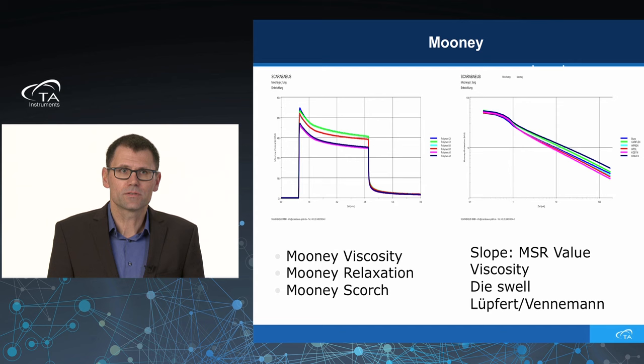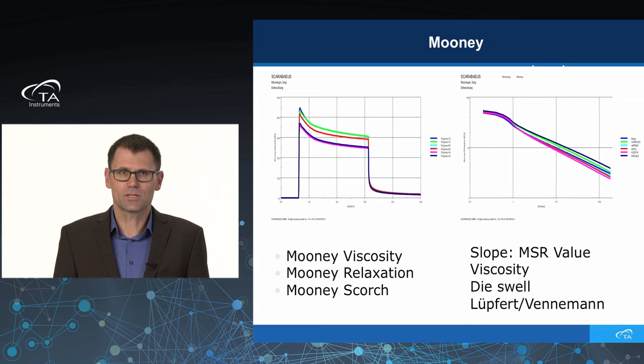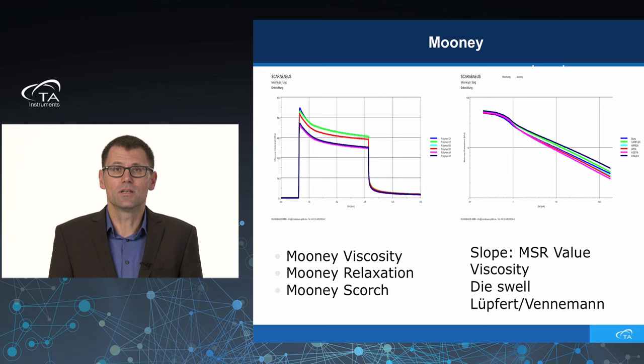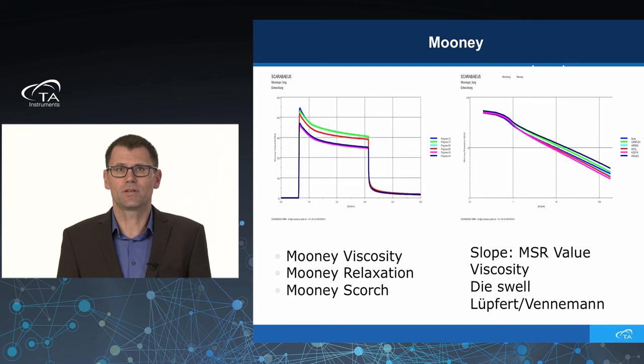When you do a Mooney viscosity test, it makes definite sense to add a two-minute relaxation test. The relaxation test gives you more information about elasticity and die swell. When you plot it on a log-log scale, you get curves where the slope of such a curve is the MSR value — the Mooney Stress Relaxation value. I will come back to this value in more detail later.